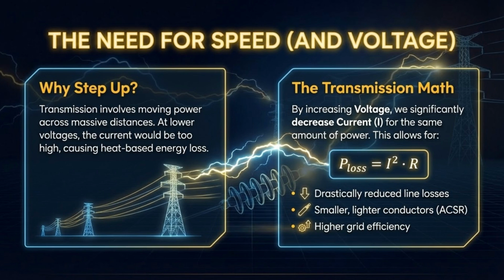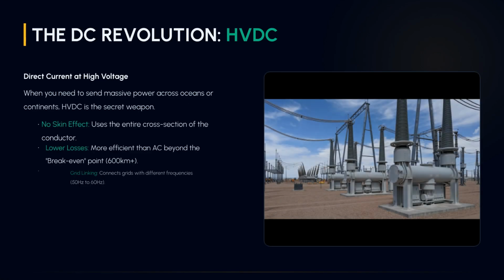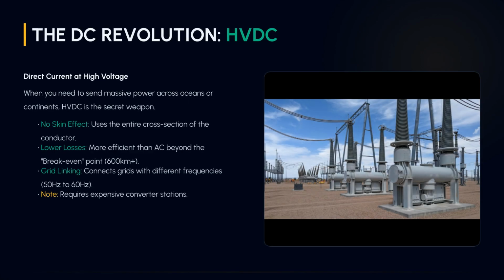The core principle is minimizing heat-based energy loss over massive distances. The DC revolution, or high voltage direct current, HVDC, is vital for long-distance power transfer, especially across oceans. HVDC eliminates the skin effect and offers lower losses beyond 600 kilometers. It also links grids with different frequencies, but requires expensive converter stations.